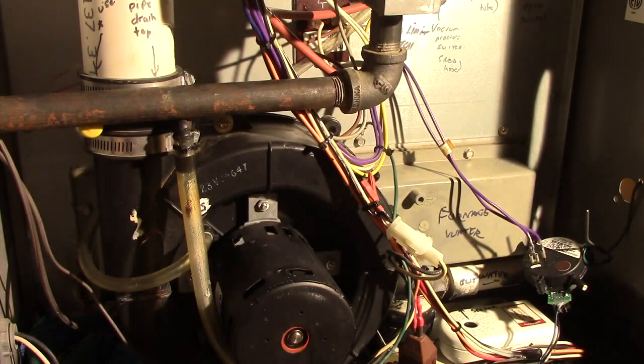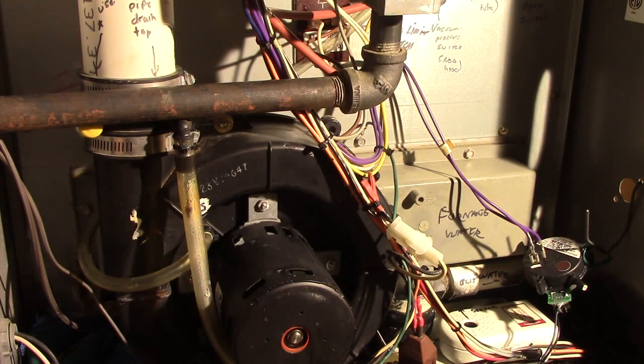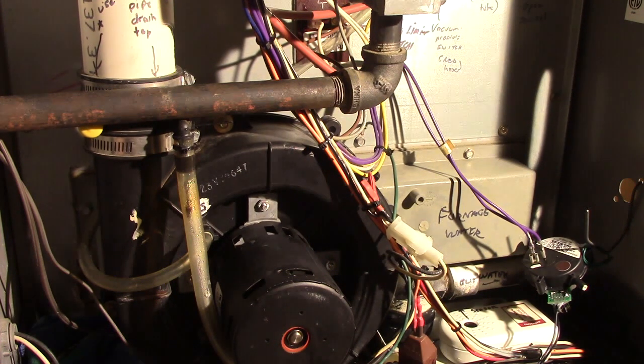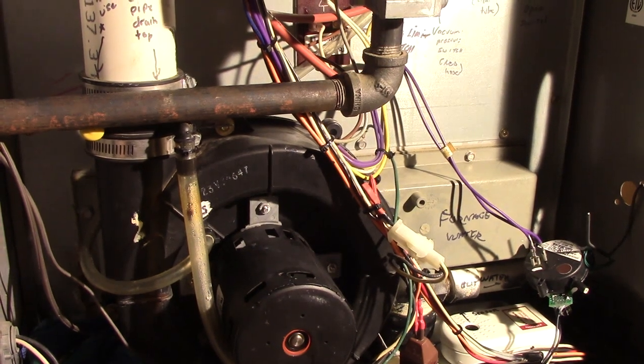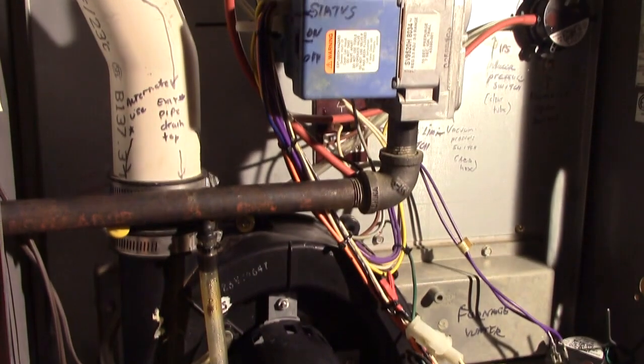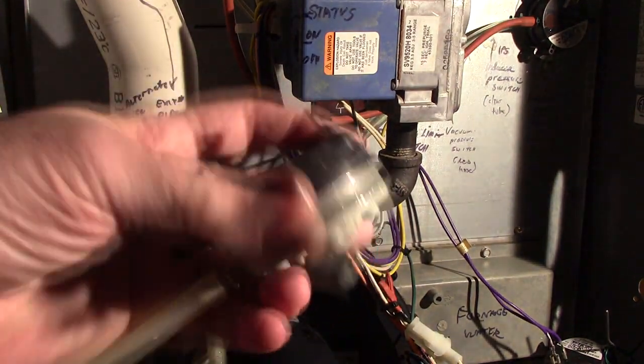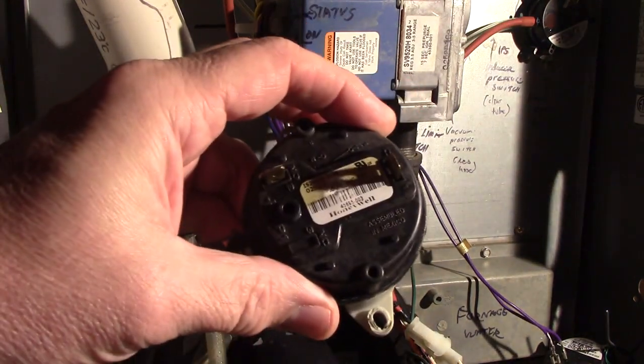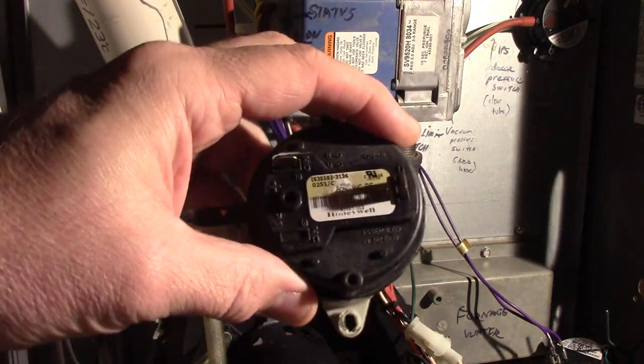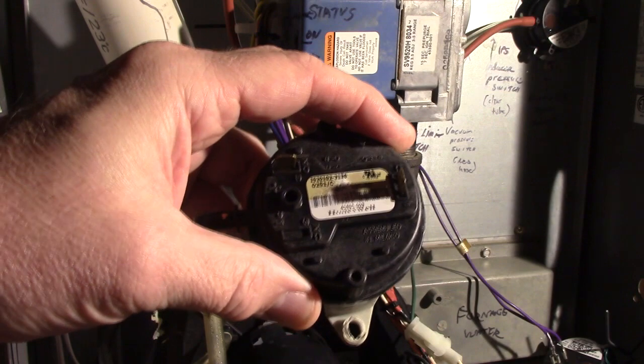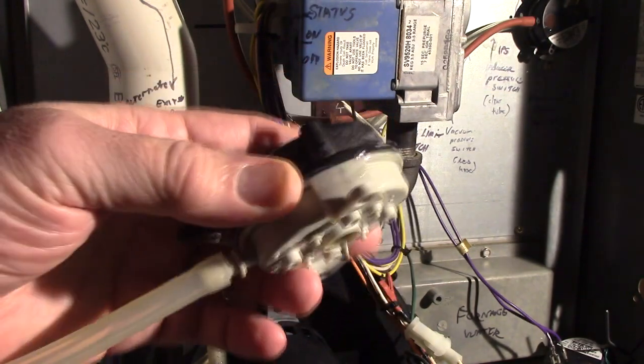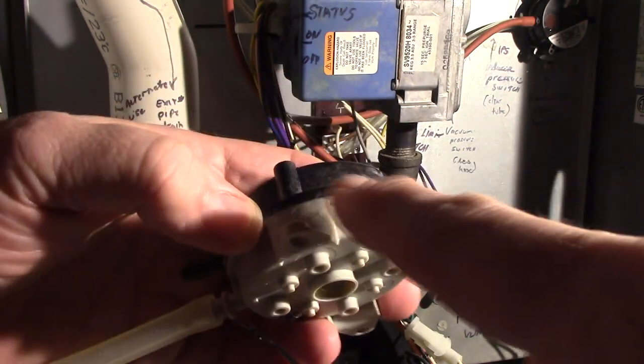It's three in the morning, you wake up cold, your furnace is failing, and you get a code of 63 or 64 because your pressure switch has failed. Really typical - they fail at the worst time they could.